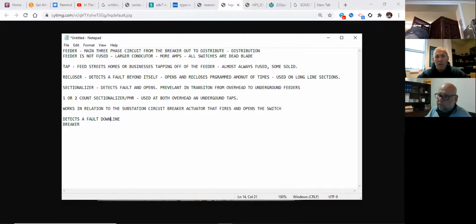We'll go on the same scenario of instantaneous and timed that we talked about before. A fault occurs on my line. The 2-count sectionalizer detects a fault downline. That fault also travels to the breaker. The breaker sees it. What's the first operation a breaker does? Instantaneous. All right, breaker, instantaneous.